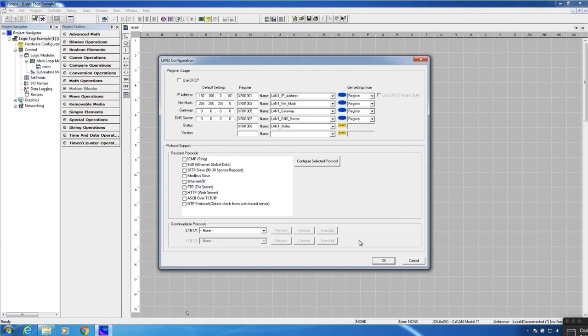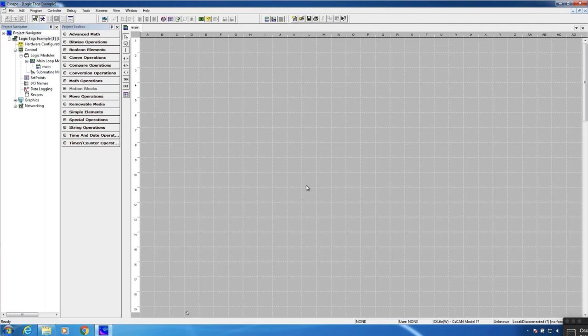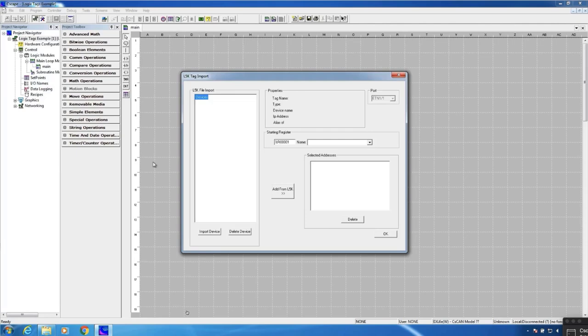Currently in the Cscape configuration, to support exchanging global tags with a Logix CPU, you need an L5K file — an export file from a Logix 5000 program in the Rockwell system. That's a prerequisite. If I'm in control of the program in the Logix CPU, no problem. If I'm doing an integration job, I need to make sure I have access to that L5K file to know what global tags are in the processor I'll be interfacing with. From Cscape, you access the L5K import from the program menu: 'Import Tags from L5K File.' Select that, and the L5K Tag Import dialog pops up.